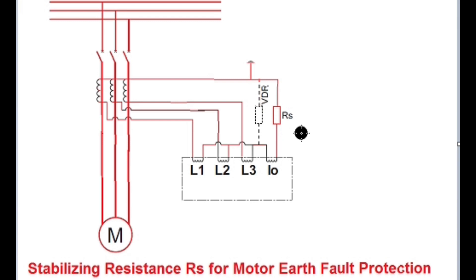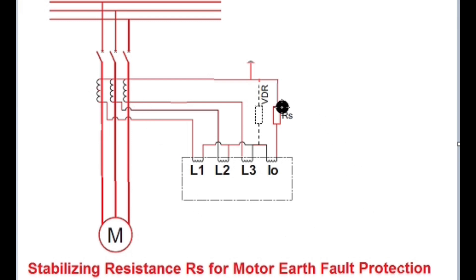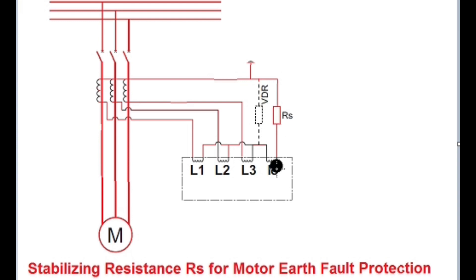The purpose of the stabilizing resistance is to provide stability during starting of the motor if either of the CTs saturate. In this video I will discuss how to calculate the value of the stabilizing resistance RS and also whether the VDR — that is the voltage dependent resistor or metrosil — is required in parallel with the resistance and earth fault coil or not.